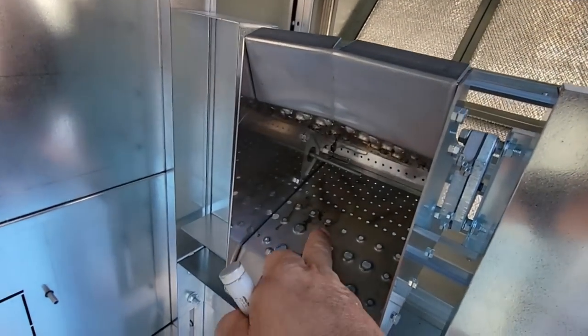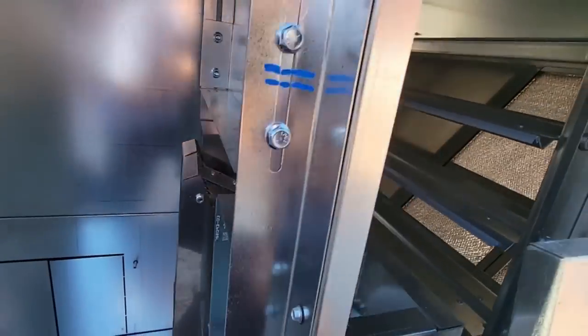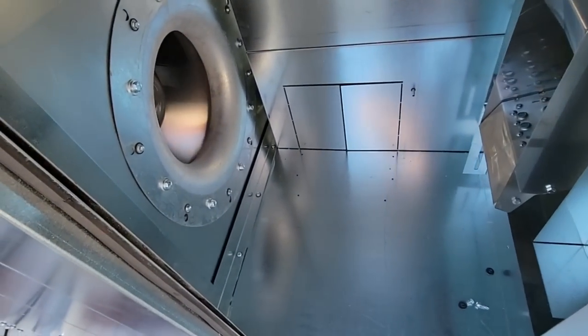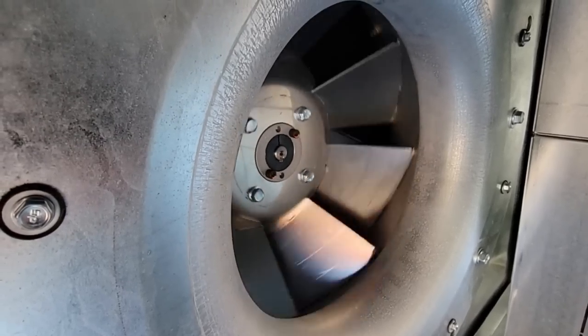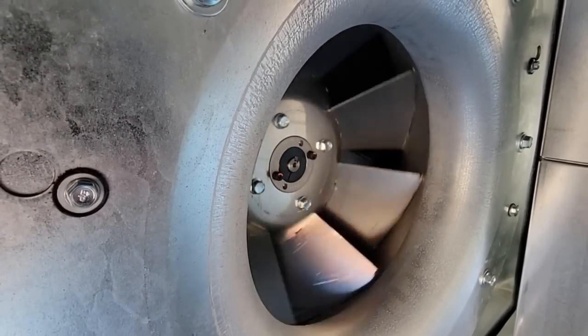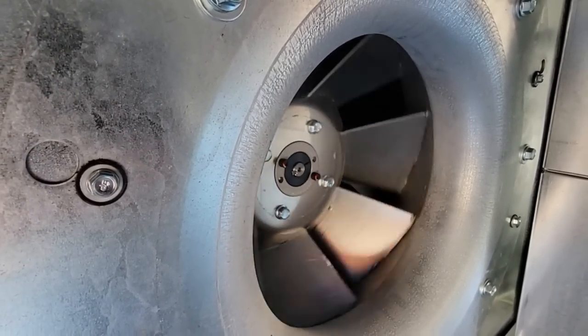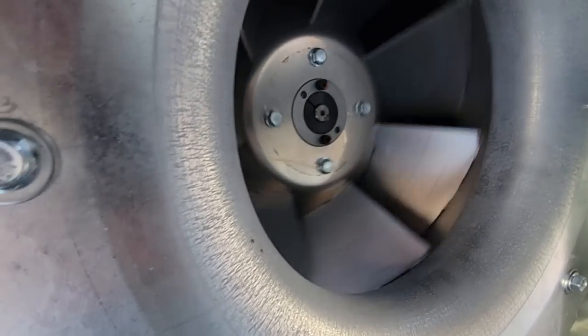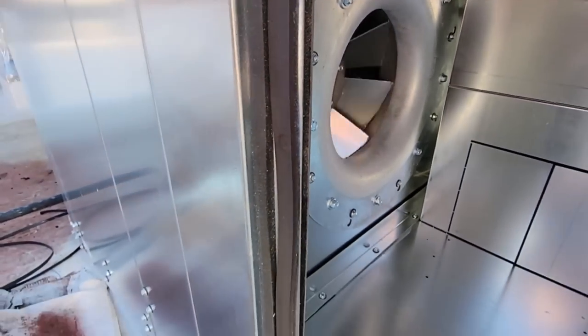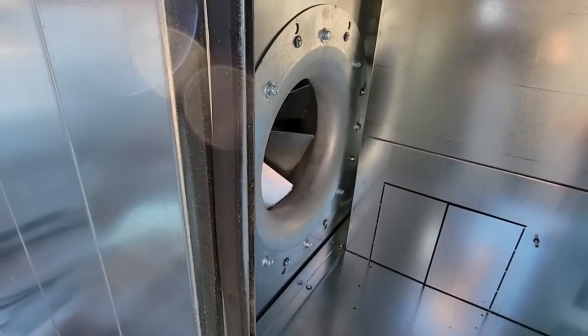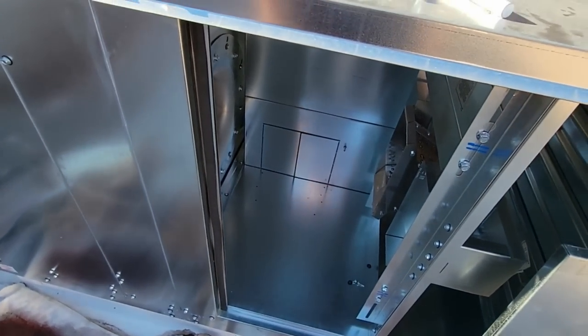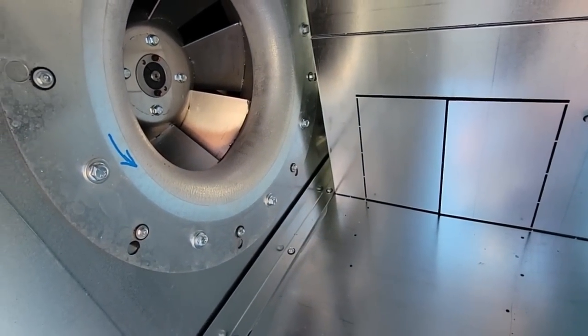You can tell the fan needs it, there's a lot of gunk build up there. We did verify it's spinning the right direction, I believe. This one here actually works like you would figure. It cuts into the air and pulls it through. So this is more of an inline, more than the traditional exhaust. So I'm wrong on that. But yeah, that's going the right direction. Once again, put a little arrow in there.